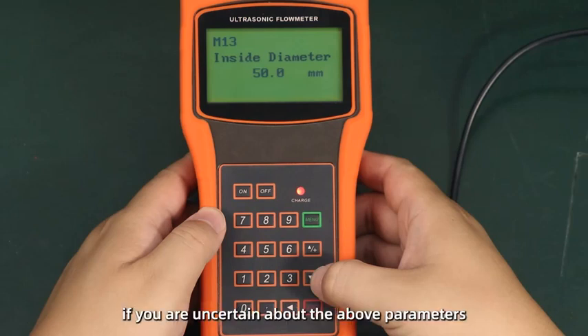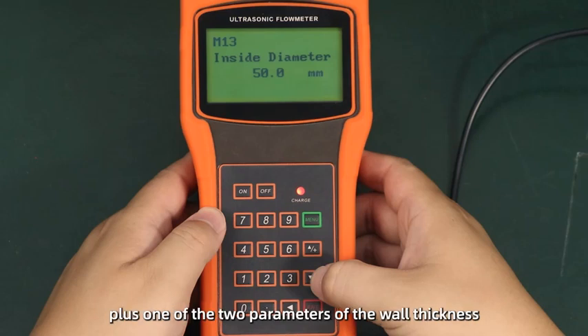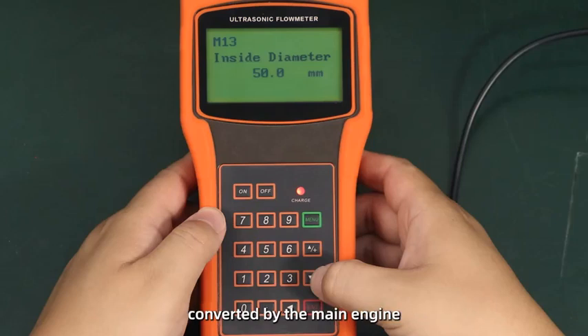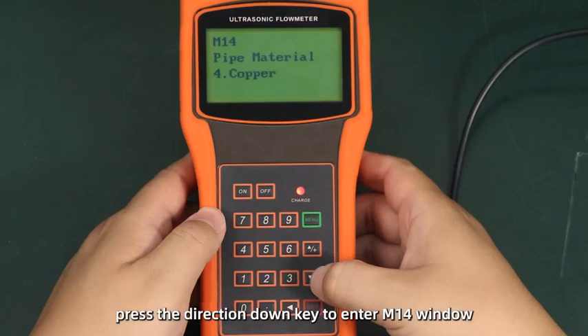If you are uncertain about the above parameters, you can determine one of the two parameters of the external circumference and the external diameter of the pipeline, plus one of the two parameters of the wall thickness and the internal diameter of the pipeline, and enter two confirmed parameters, and the other parameters will be automatically converted by the main engine. Press the direction down key to enter M14 window.